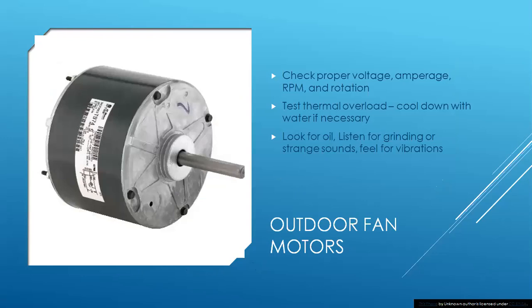So our outdoor fan motors, very important. Watch for any kind of oil where your bearings are leaking here. Check proper voltage. That's huge. If you start exceeding 253, you will sustain damage over time to your condenser fan motor, actually your entire unit. So that's why proper voltage is important. Also check your amperage. Your amperage will be on the side of the fan motor. It'll also be on the data plate.